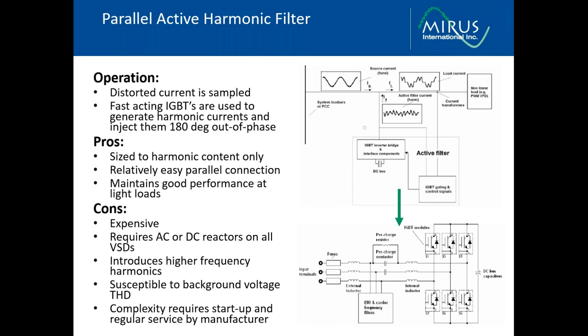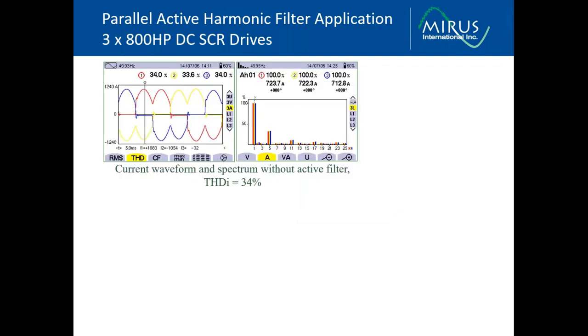Again, these are expensive. In order to perform well, you must have an AC line reactor or a DC link choke on the variable speed drive to reduce the harmonics that the variable speed drive is drawing. Like the AFE drives, they also introduce high frequency harmonics due to the switching of the IGBTs that are directly connected to the power system. They can be susceptible to background voltage distortion. And again, they are quite complex, requiring startup and regular service by the manufacturer. But they can be reasonably effective if applied properly in the right application.